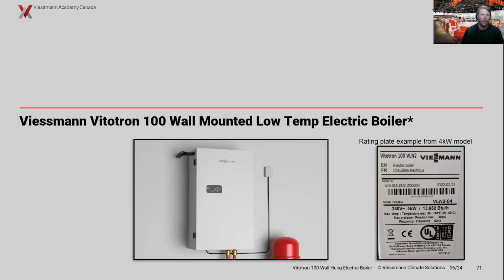We're not too concerned with poor water quality and exchange of that water all the time. Whereas if you were using tap water, now we need to treat the tap water before we add the glycol, to make sure we are putting the right water quality in the system, especially with electric elements. Think of it like electric water heaters. We all know that calcium and things can get burned right on that element. And this is going to get a little bit hotter, a little more concentrated in a smaller vat of water, so that can be exacerbated a little bit easier with more usage than you would see with your typical DHW electric tank. 100%.